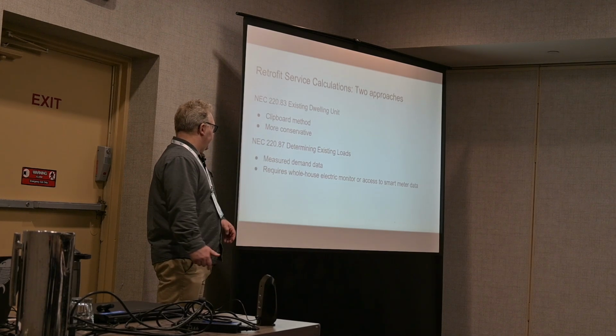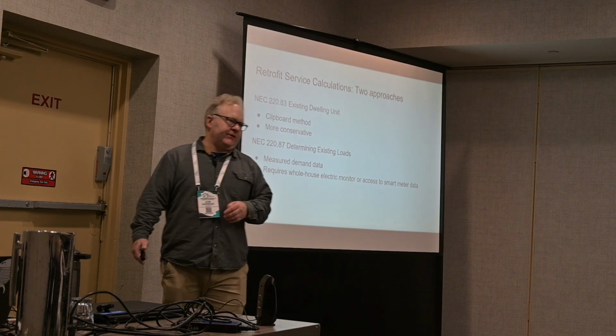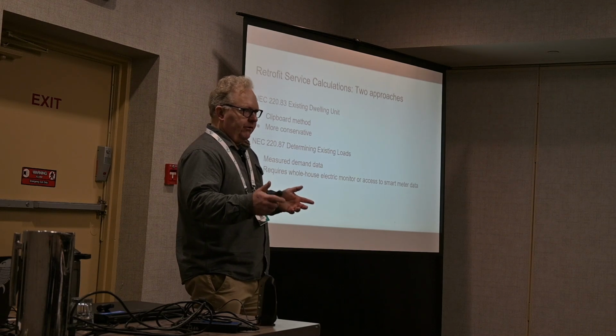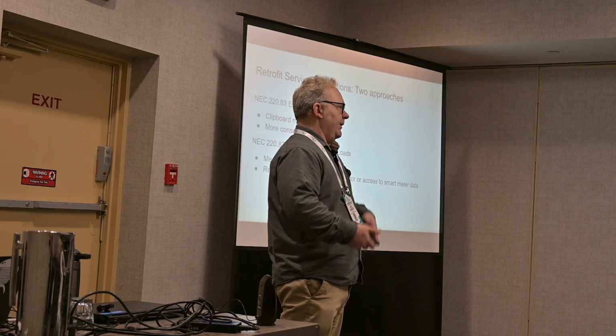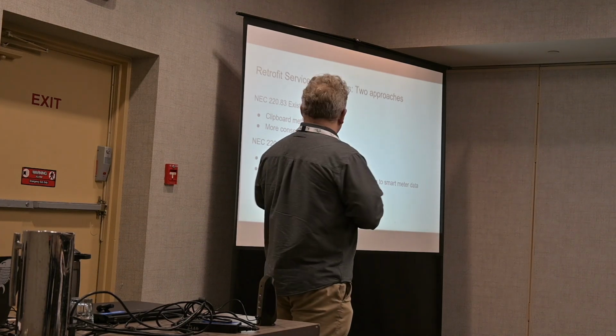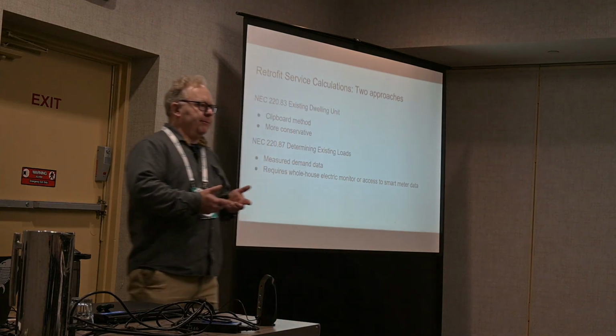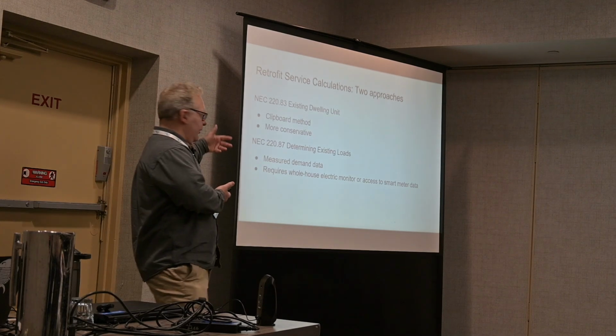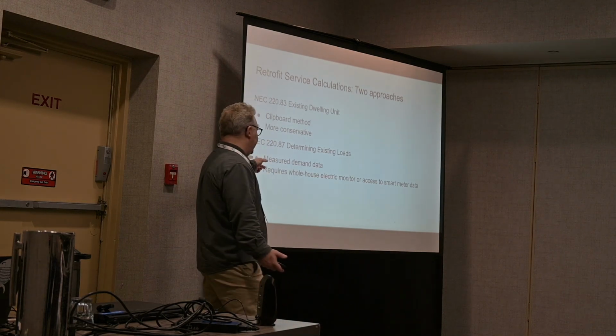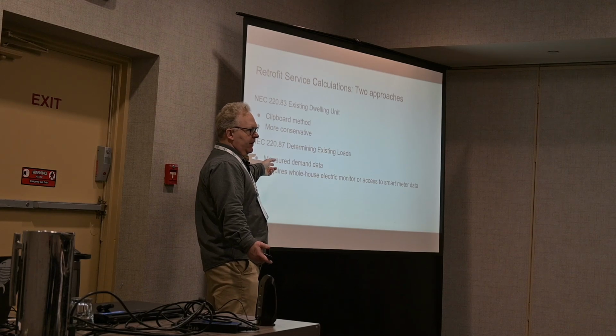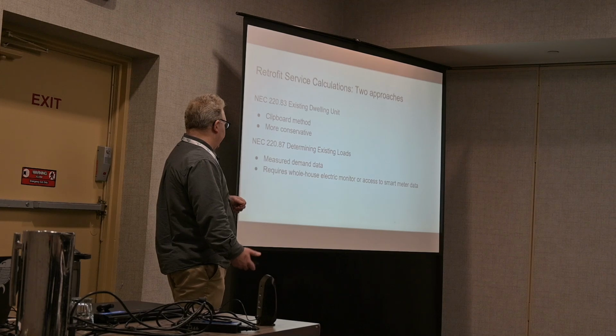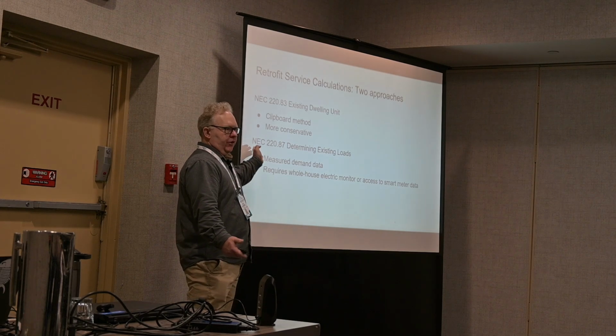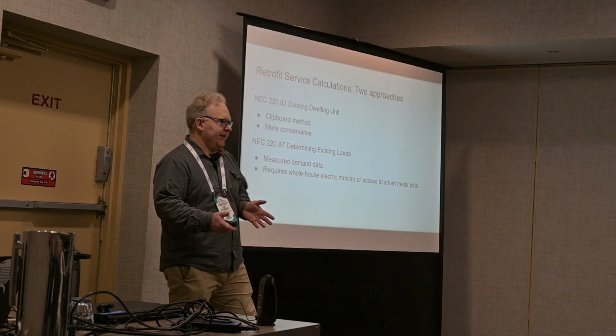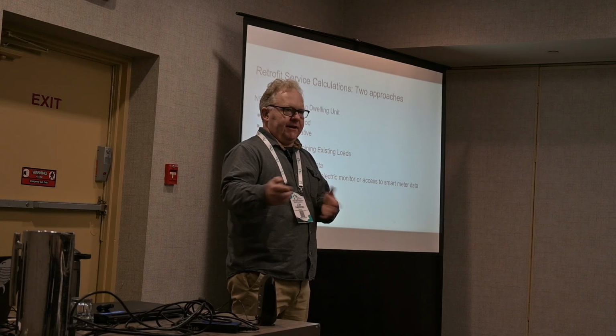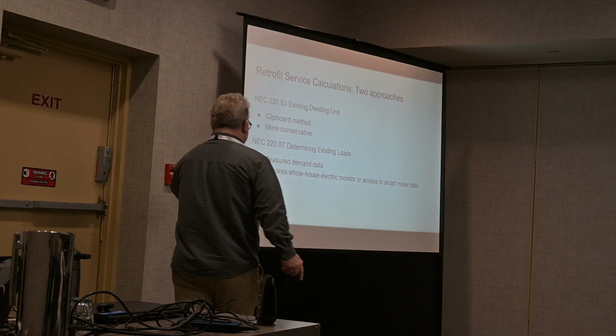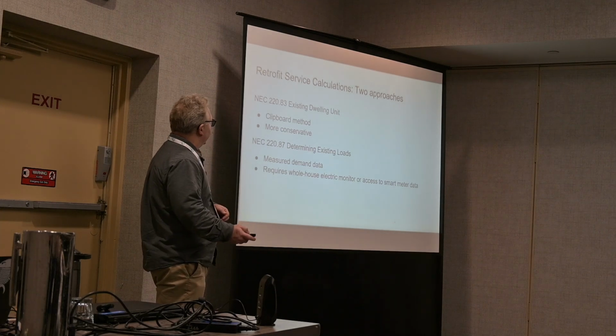The other one is under NEC 220.87, determining existing loads. And this requires energy monitoring data. This was used a lot more commonly in commercial settings where people already had devices in place that could measure peak demand. But now that we have devices like Emporia monitors that can monitor people's real-time electric use, this can give us the data that we need, and with a really quick calculation can tell us, okay, this house has plenty of extra panel capacity or not. In theory, this should also be very easy to calculate if we can get access to smart meter data. I have never succeeded in getting any of this from my utility, so I've ended up relying on home energy monitors that I've put in on my own.